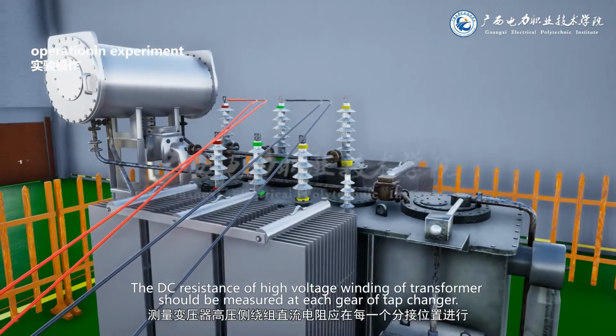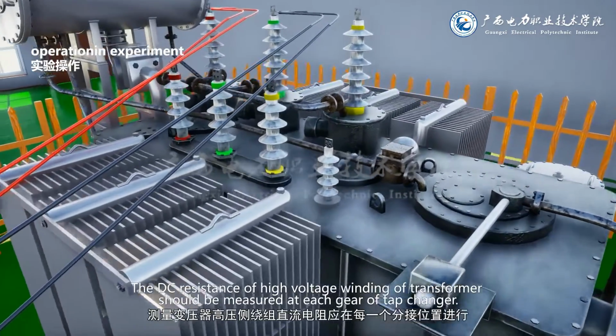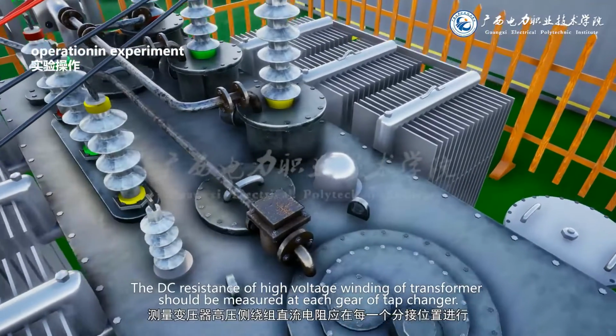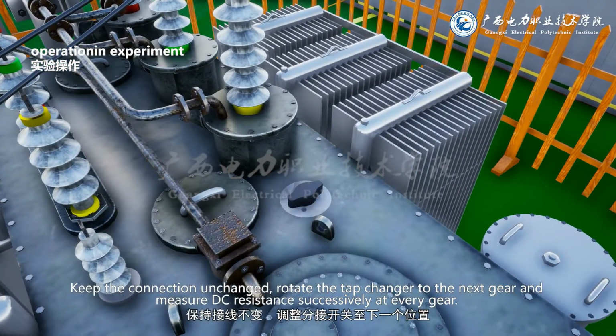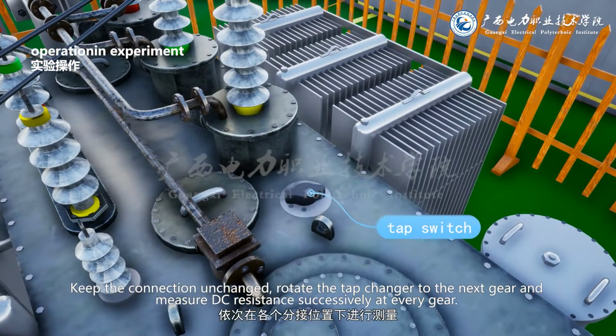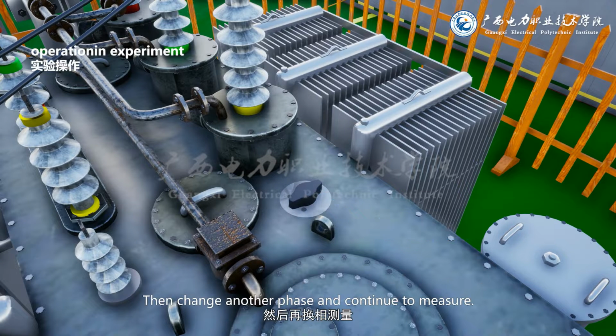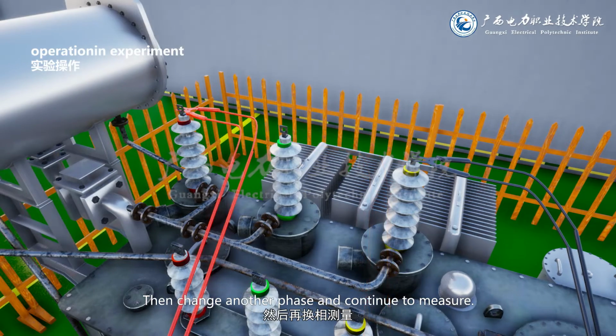The DC resistance of high voltage winding of transformer should be measured at each gear of tap changer. Keep the connection unchanged, rotate the tap changer to the next gear and measure DC resistance successively at every gear, then change another phase and continue to measure.